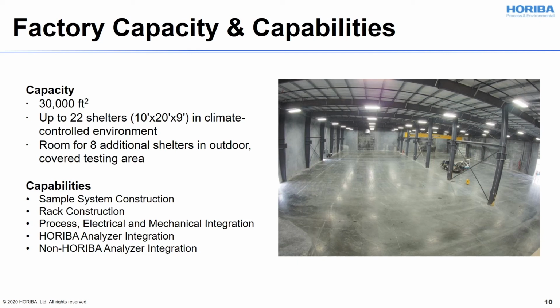Some of the capabilities: we have sample conditioning system construction that we can do in there. We can do rack construction, again, shelters, enclosures of any kind, all of the process electrical and mechanical integration. We can do HORIBA analyzer integration, obviously, but something we really want to focus on is that we have the capability and the experience to integrate non-HORIBA analyzers. So if you have a GC, a mass spec, or a turbidity analyzer, say, that you may want to have installed, we have the capability and the experience doing that. Again, if you have any questions about these types of things, definitely reach out to myself or Mick.